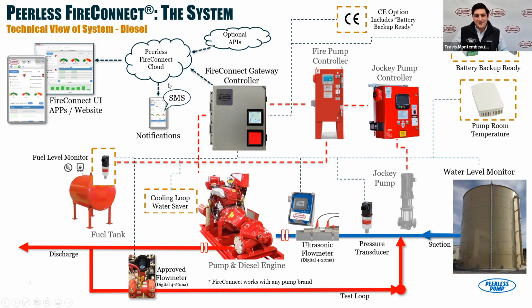Now, we all know that we're not going to spend every waking minute looking at those dashboards, looking at those apps. So we want to be alerted when there are condition changes. That's where the SMS and notifications component comes in. If the pump room temperature drops to 40 degrees Fahrenheit, we take that input into the gateway and send it to the cloud, and we want it to send us a text message saying, hey, your pump room temp is low, or your fuel level is low, or your water supply tank level is low. These are outputs that you normally would only be able to see if you're physically in the fire pump room itself, boots on the ground in there. We want to be able to see that without having to get out of bed, effectively. Look at the app, look at the text messages we get, and take that information there.